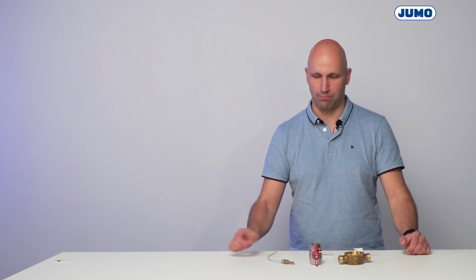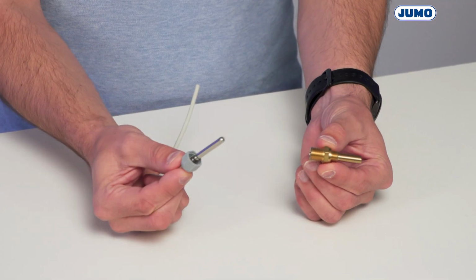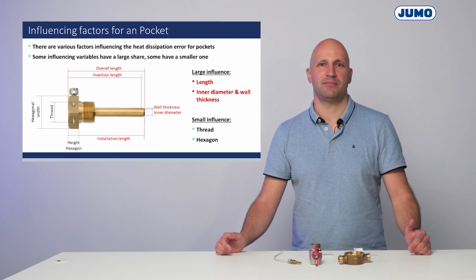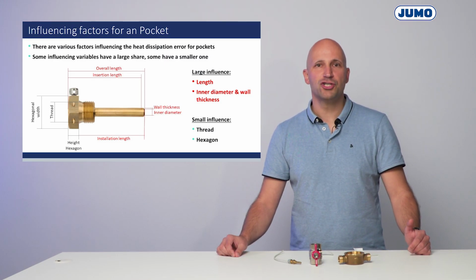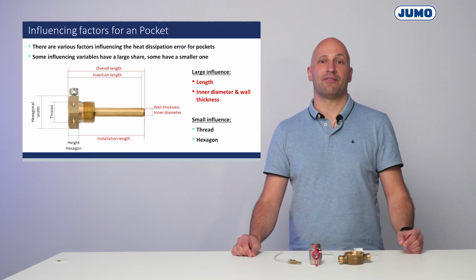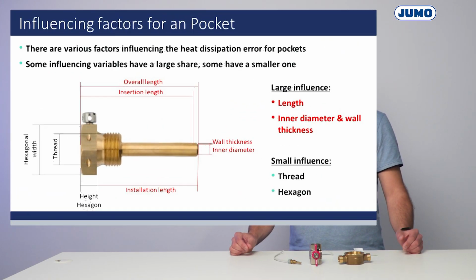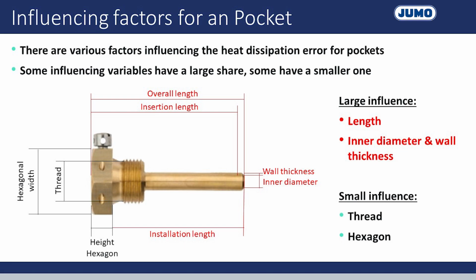or cold meters. Another factor that is often not considered is the use of so-called immersion sleeves or pockets. These pockets protect the temperature probe and make it more robust, but they also affect the measuring accuracy. How exactly? The length of the pocket and its internal diameter play a key role. A pocket is an additional thermal resistance. The temperature probe is less well coupled to the true temperature, and the pocket has an additional heat conduction error. The heat conduction error is particularly pronounced with shorter pockets. However, the height of the hexagon, the wall thickness, and the tolerance of the inner diameter of the pocket also determine how precise the measurement is.